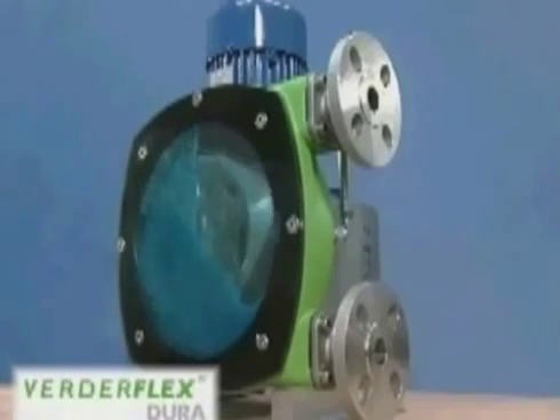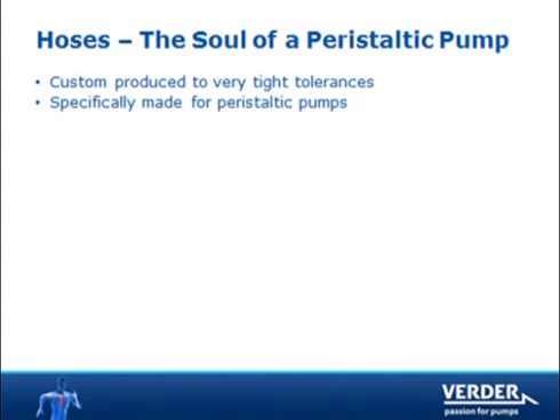Here you can see the pump in action. A slow speed rotor turns and compresses the hose twice per revolution. The hose exterior is cooled and lubricated with glycerin-based VerderLube. Peristaltic pump hoses are made to very tight specifications for maximum working life.